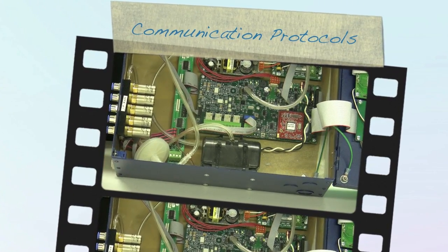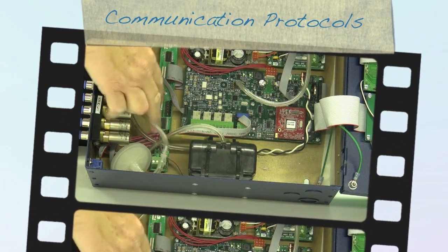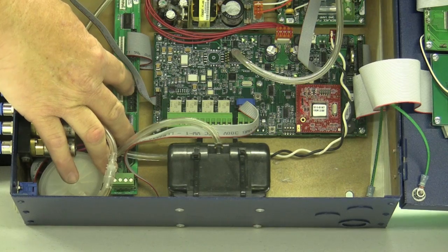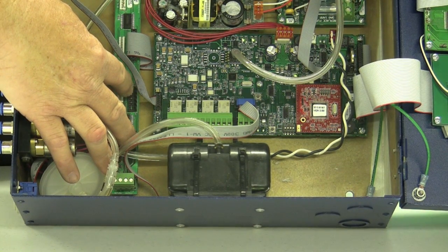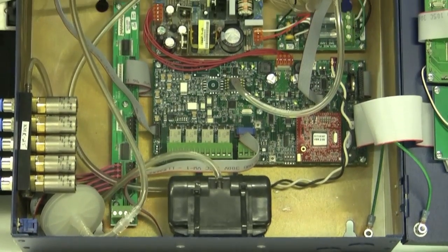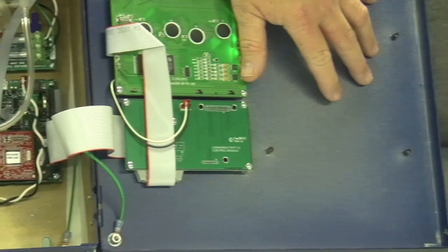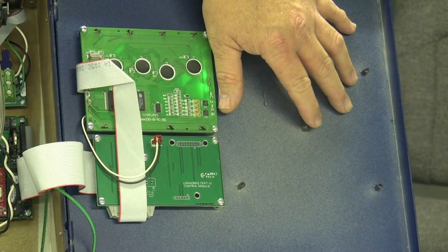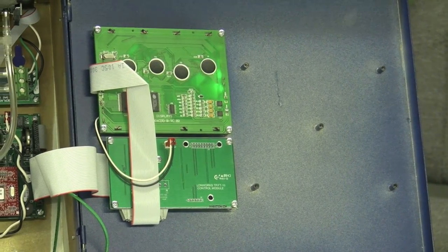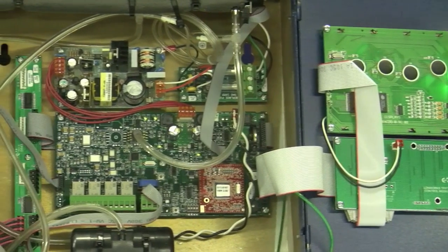It also has communications capabilities, from a very simple 4 to 20 board which would plug in right here where these two plugs are. On one leg of the 4 to 20 output you get the PPM reading, and on the other leg you would get the zone reading. You can also add LonWorks, which would bolt inside the front cover, or you could add JCI Metasys N2. There's also a BACnet package available, so as peripheral communications we have just about everything available out there that this unit will talk to.